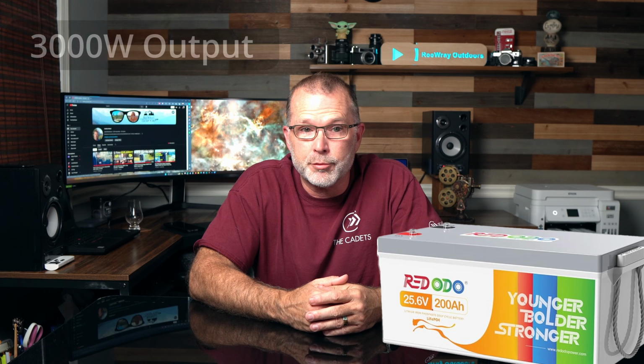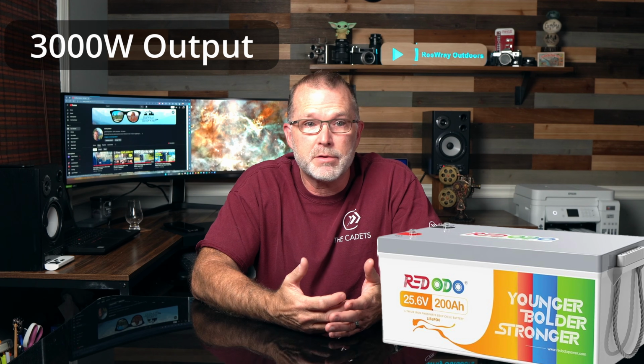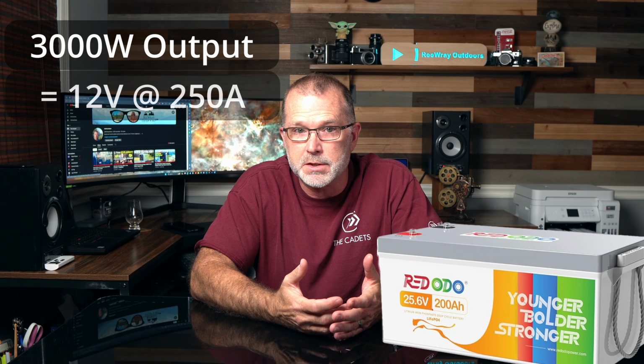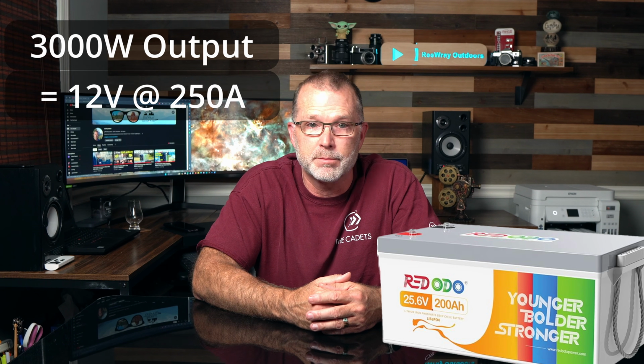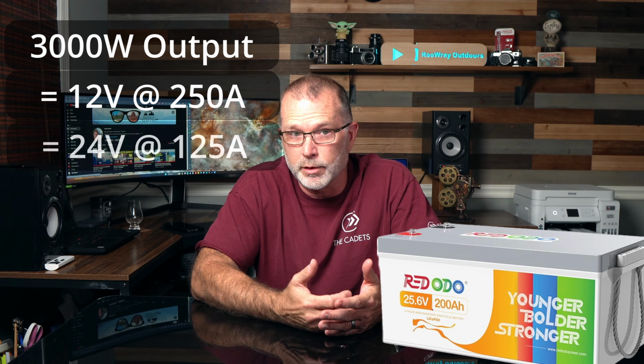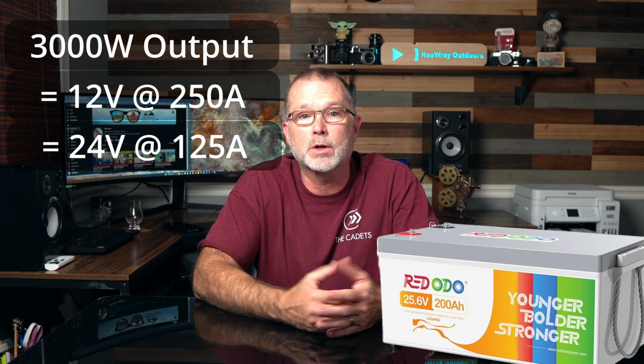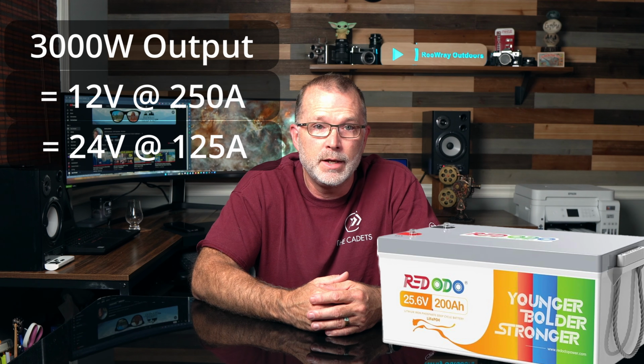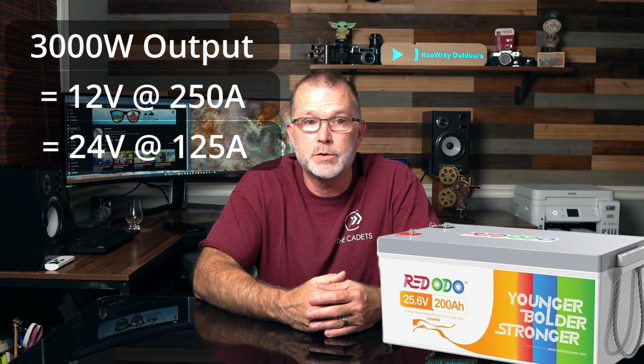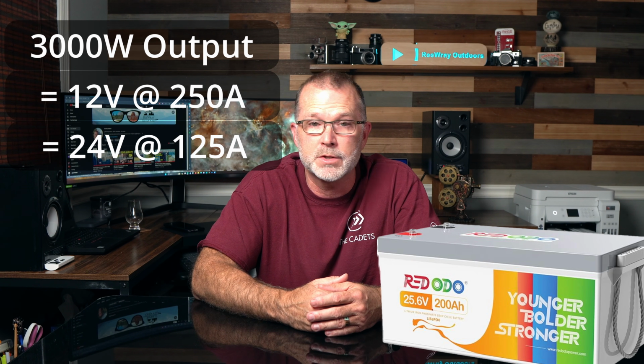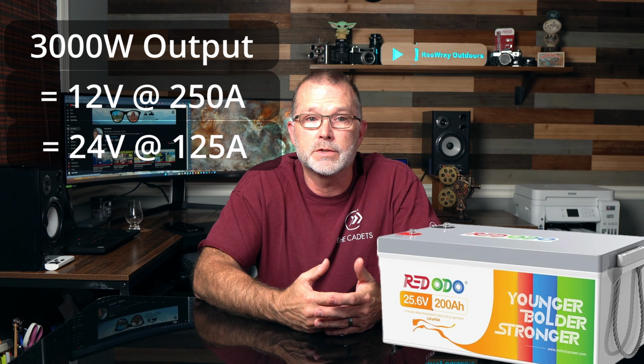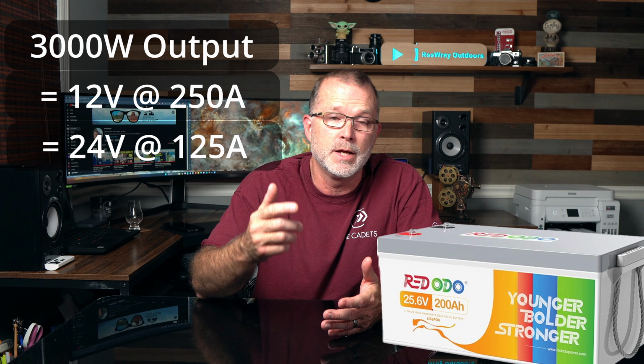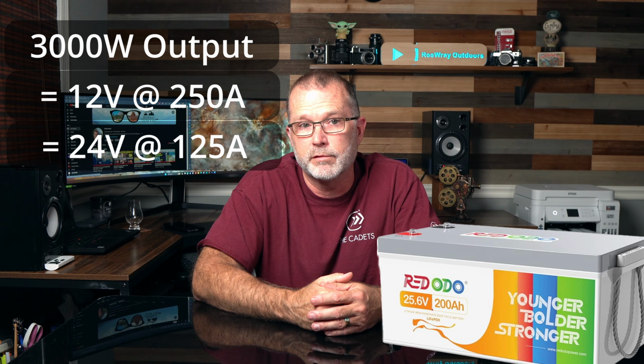So take, for example, 3,000 watts of output. To get 3,000 watts of output from a 12 volt system, you're going to need 250 amps to push that. But in a 24 volt system, that same 3,000 watts only requires 125 amps. That lower current means you have the option of using less expensive, smaller gauge cables, and the higher voltage is also going to have less voltage drop over the same cables versus a 12 volt configuration.